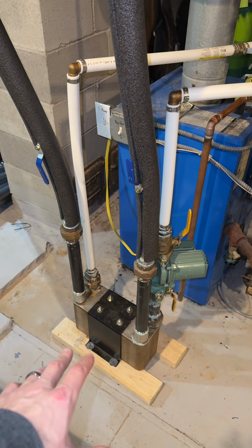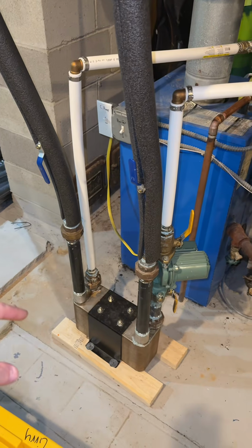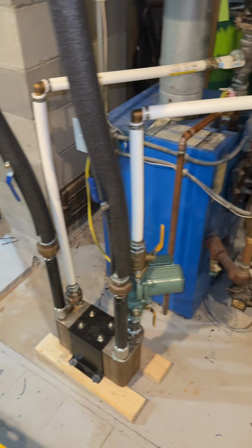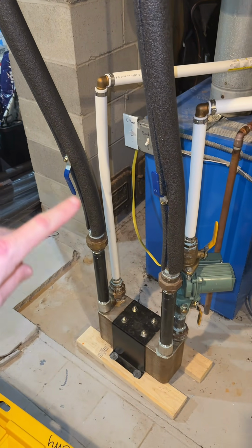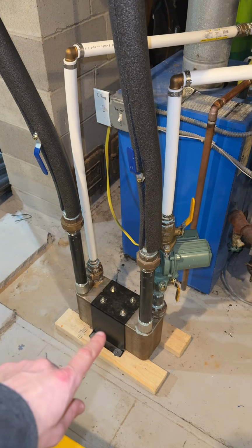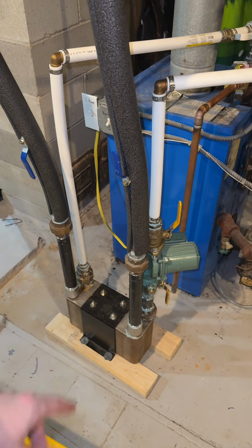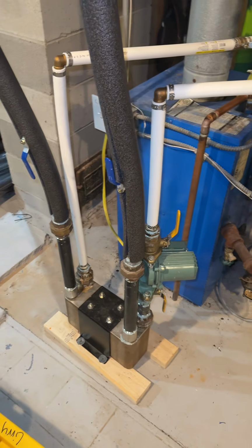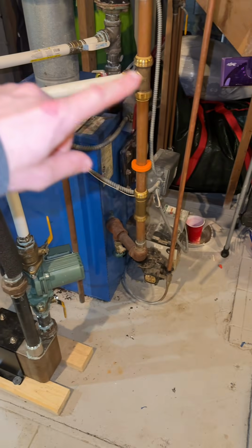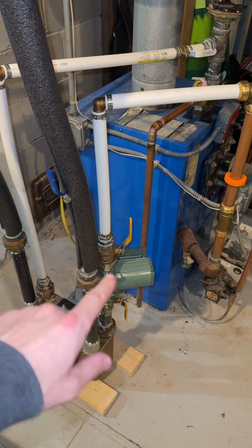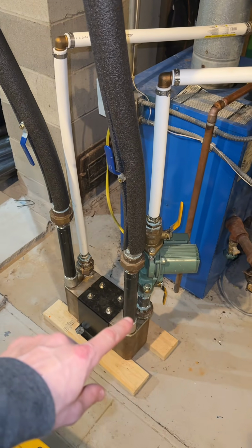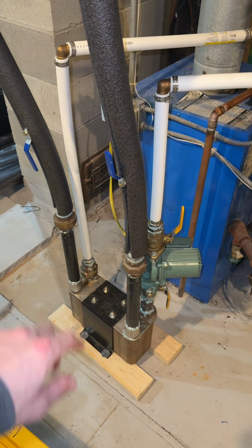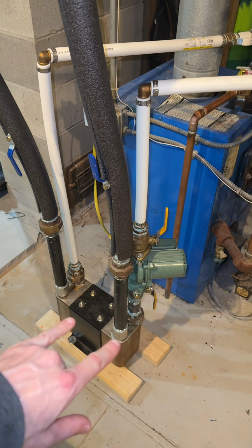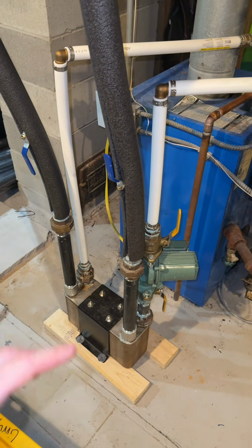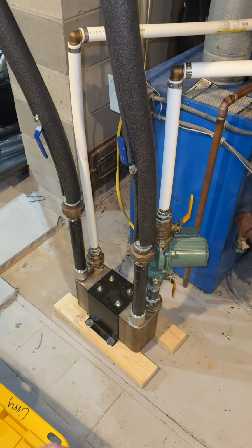So this brings me to my heat exchanger, which ties in the outdoor wood boiler to the oil boiler right here. So you have the hot water coming down here, going in through this side of the heat exchanger, back up and out to that wood boiler. You then have colder water coming down here through this pump, through the other side of the heat exchanger and going back. Now you want to have the direction of flows opposite so it's a better transfer of heat.